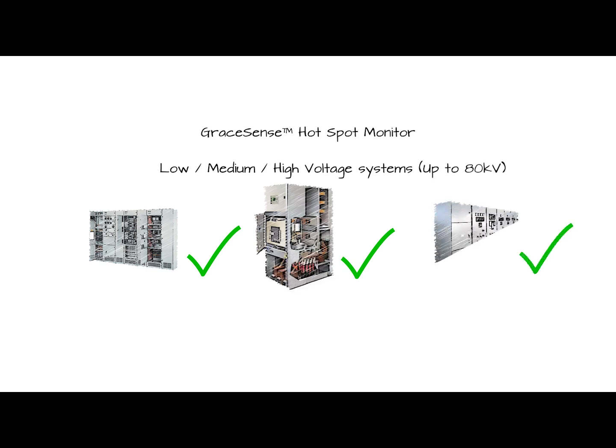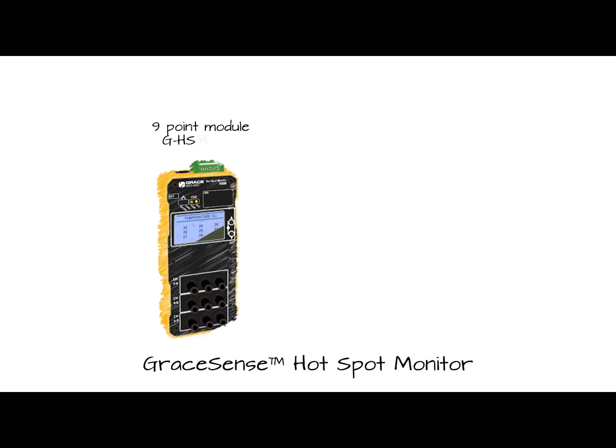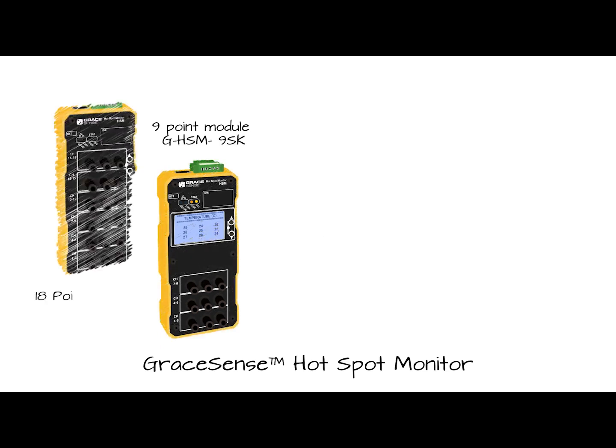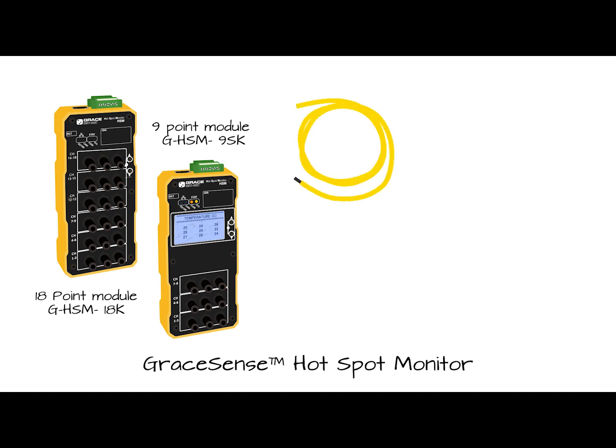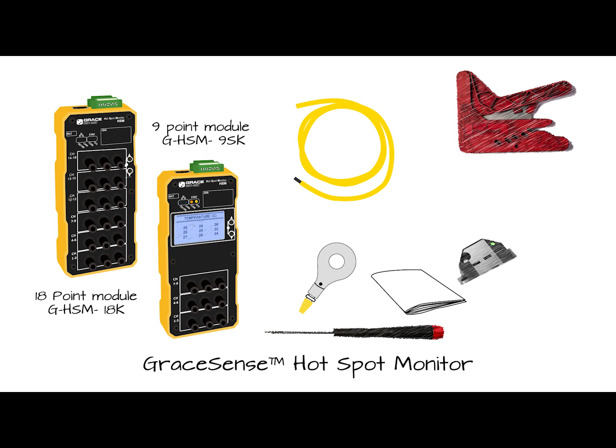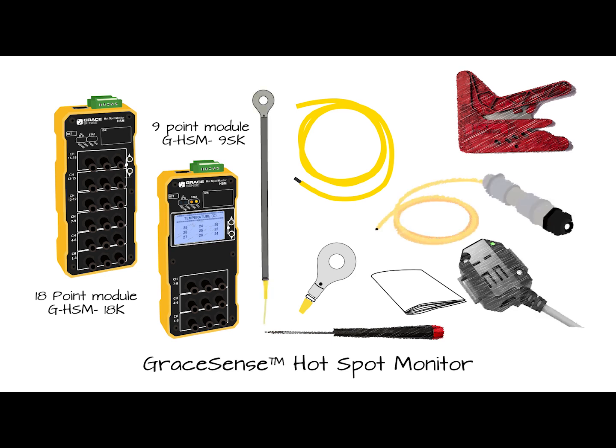GraceSense Hotspot Monitor is a reliable and affordable solution for use in environments with low, medium, or high voltage systems. The HSM is available in 2 versions, either a 9-point module with a built-in LCD display or an 18-point module. The unit comes fully kitted with fiber probes, ring-style connectors, and an installation kit. Optional accessories include a Modbus current sensor, high-temperature probes, ambient measurement attachment, custom connectors, and fiber lengths of various sizes.